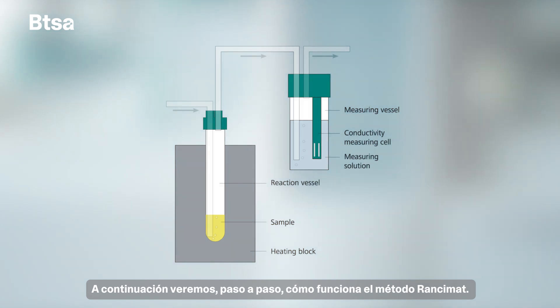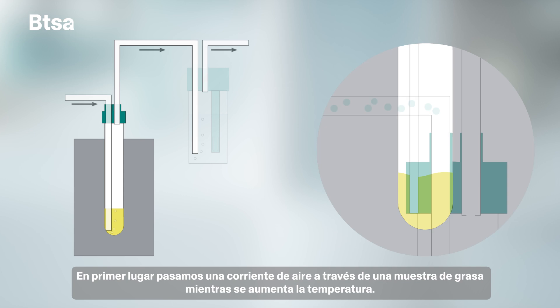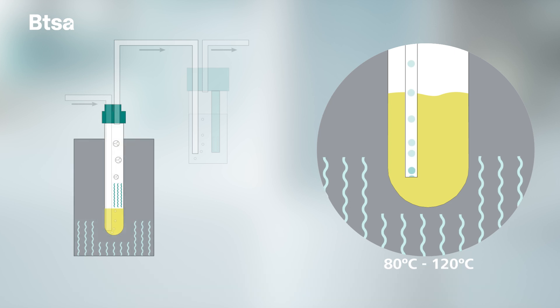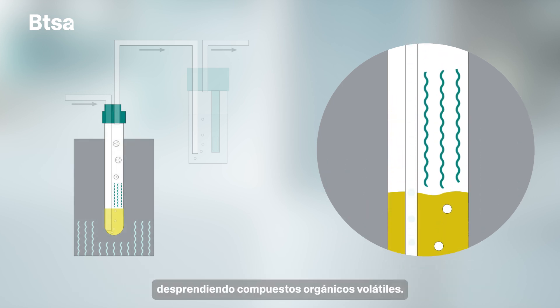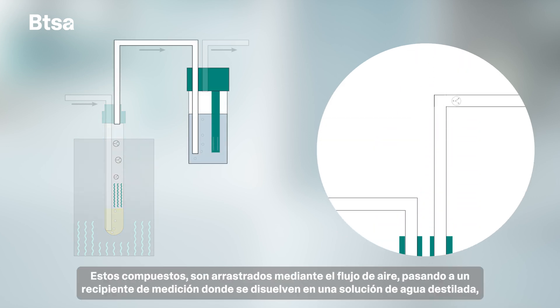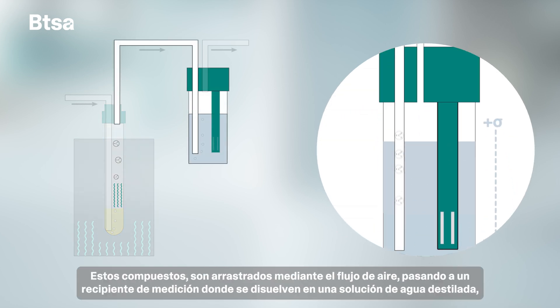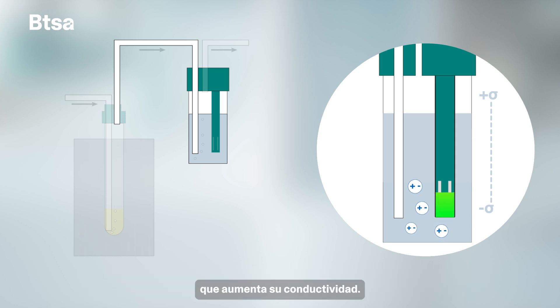Now we will see, step by step, how the Rancimat method works. First, we pass a constant airflow through a sample of fat while the temperature is increased. This causes the oxidation of the sample, releasing volatile organic compounds. These compounds are dragged by the airflow, passing to a measuring vessel where they dissolve in a solution of distilled water, which increases its conductivity.